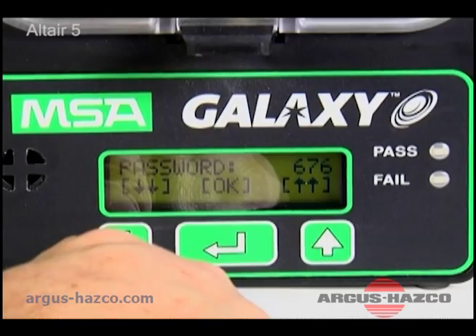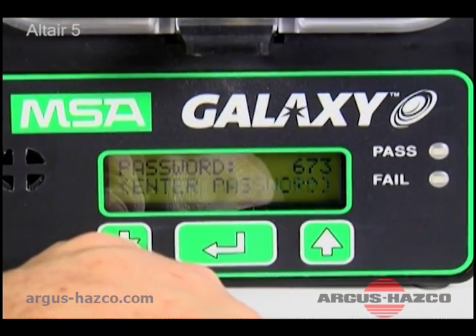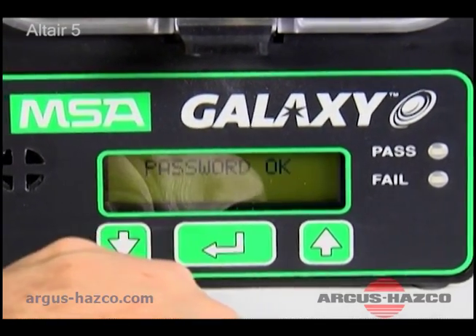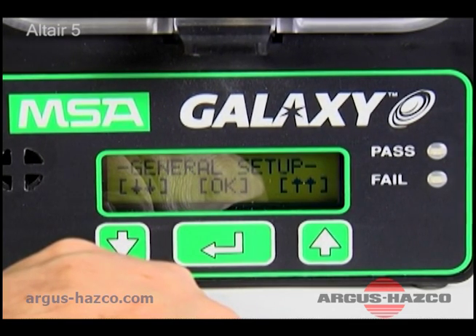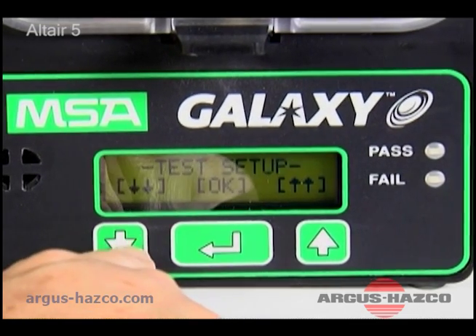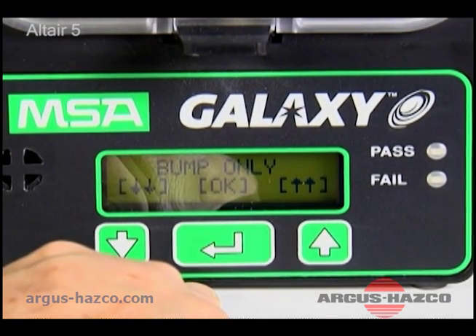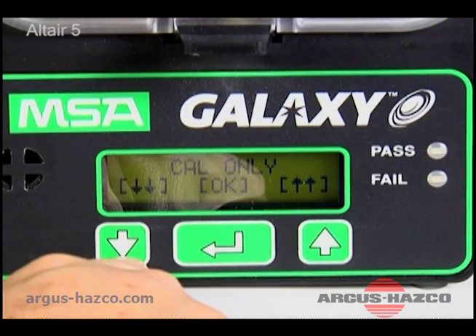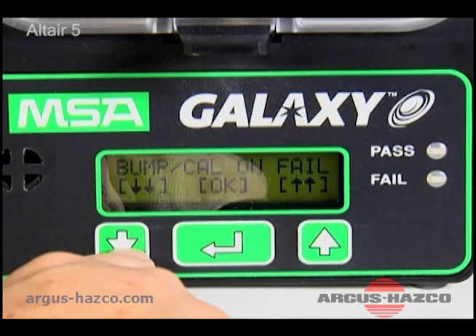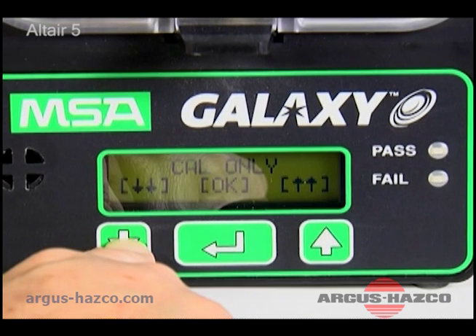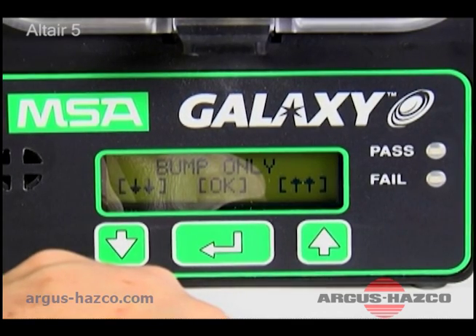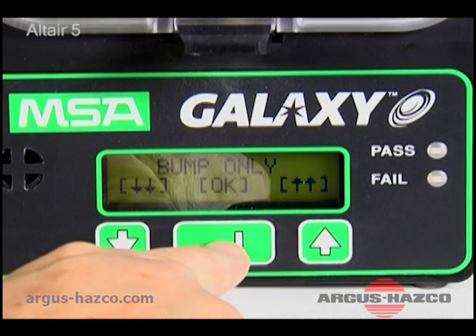To set up calibration, go to General Setup and scroll to Bump Cal. Press Enter. The Bump Cal menu offers choices to Bump Only, Calibrate Only, Bump Calibrate on Failure. The Galaxy system automatically performs the selection when you insert an instrument. For example, to Bump Calibrate on Failure, scroll to Bump Cal on Fail and press the middle button. To perform a bump test instead, simply choose Bump Only, press OK, then scroll to Exit and press Enter.